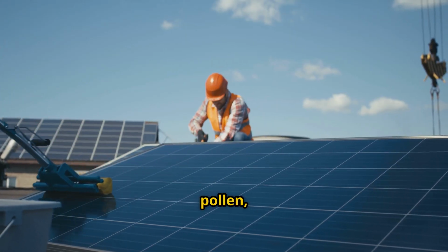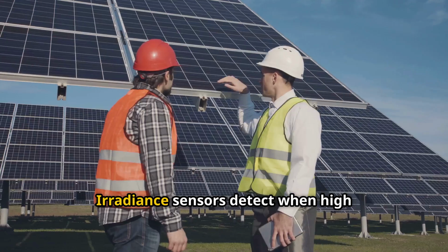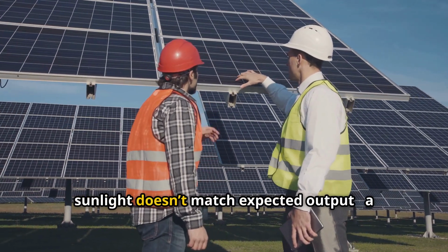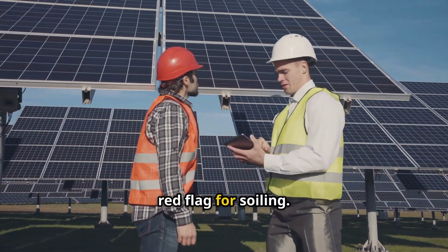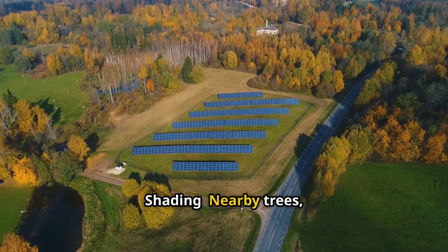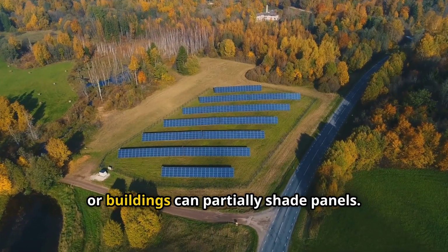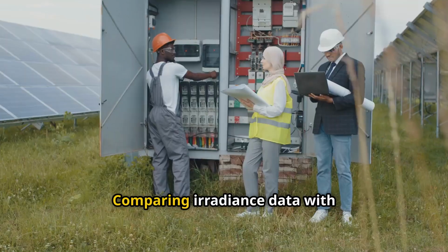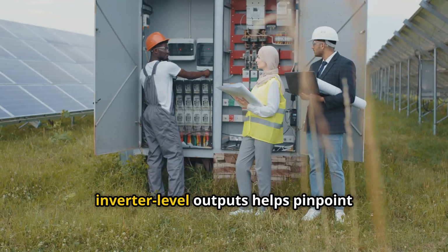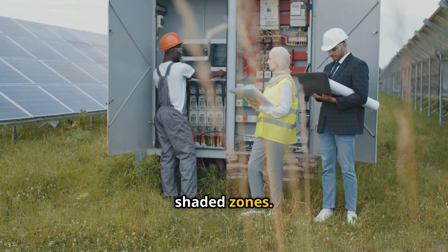Soiling. Dust, pollen, or bird droppings block sunlight. Irradiance sensors detect when high sunlight doesn't match expected output, a red flag for soiling. Shading. Nearby trees, poles, or buildings can partially shade panels. Comparing irradiance data with inverter-level outputs helps pinpoint shaded zones.